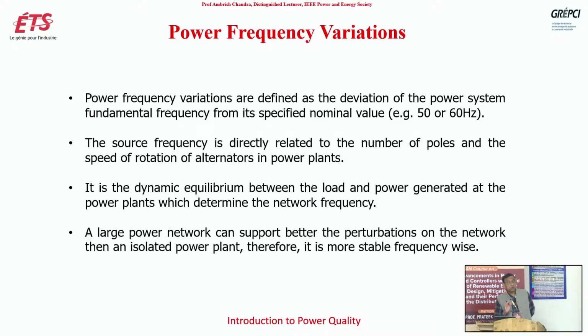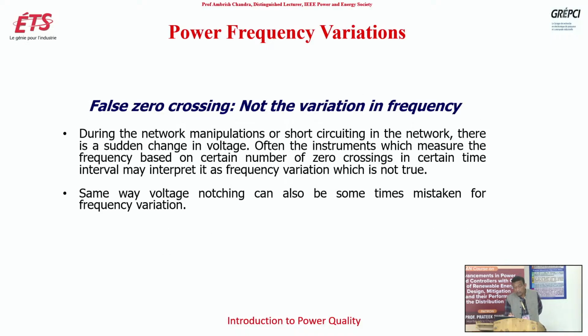This effect is not much seen for large generators, but there may be some cases, but the effect you see is false zero crossing. So if there is variation in frequency, your equipment may malfunction because of the false zero crossing, and it's the same type of thing which we have seen in voltage notching, that if there is a big notch crossing the zero, it will be a false zero crossing. Okay.